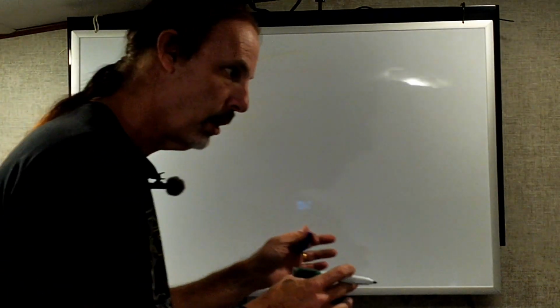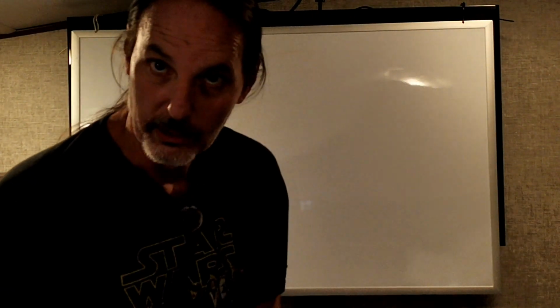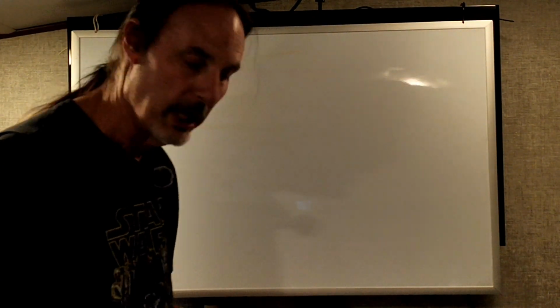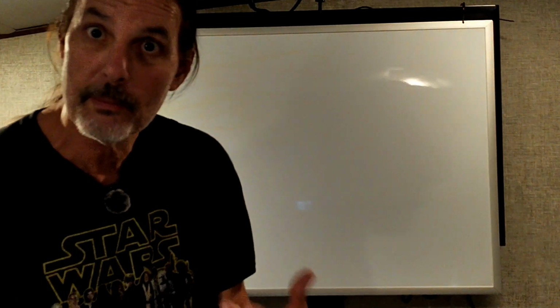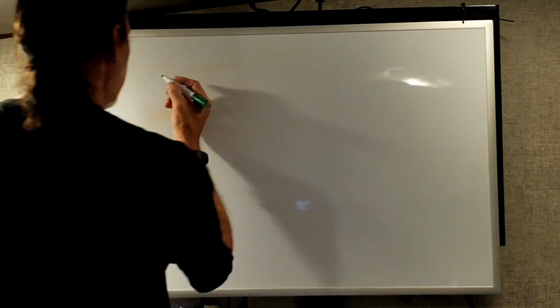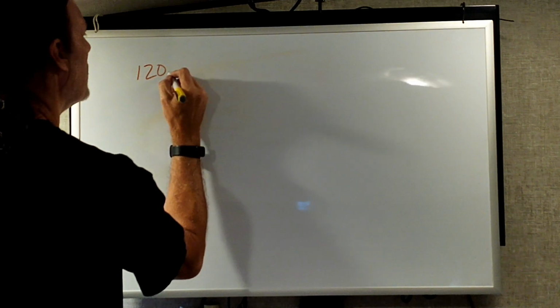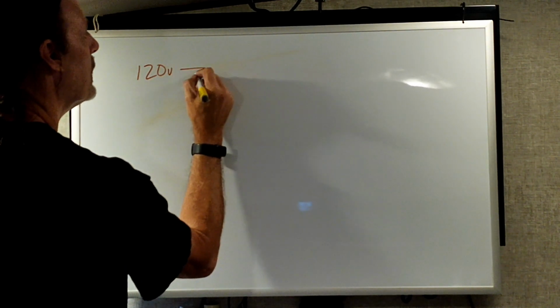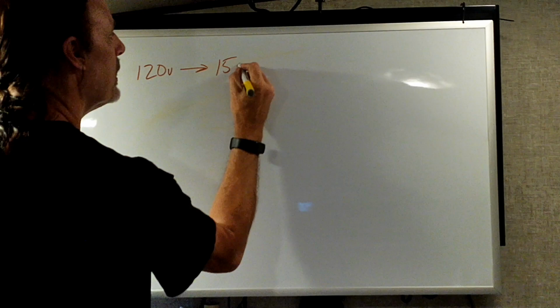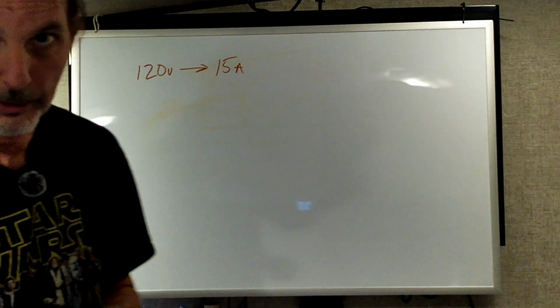We're going to start with a standard, assuming that most of you need to run power through a standard wall outlet. That means that you're probably going to want at least one wall outlet. So I'm going to do everything based on one wall outlet, as an example, so that you understand how to calculate what you need to know. So let's assume, first of all, that we have 120 volts, and you need a 15 amp standard wall plug.